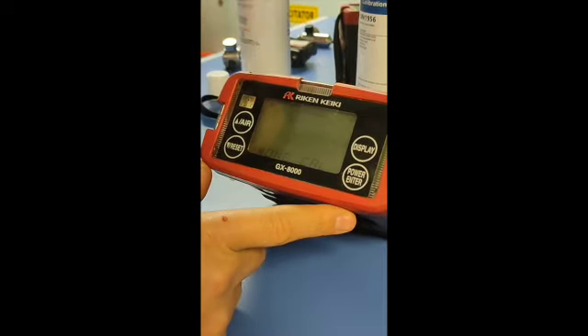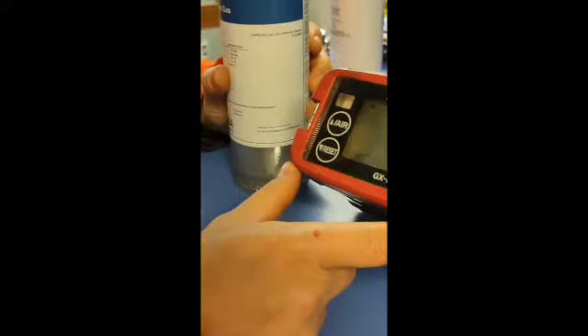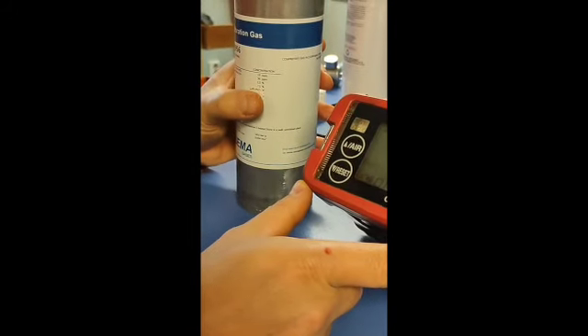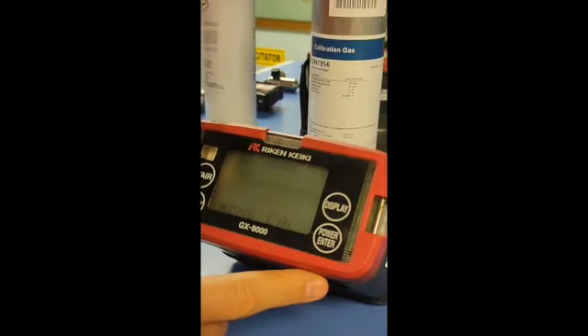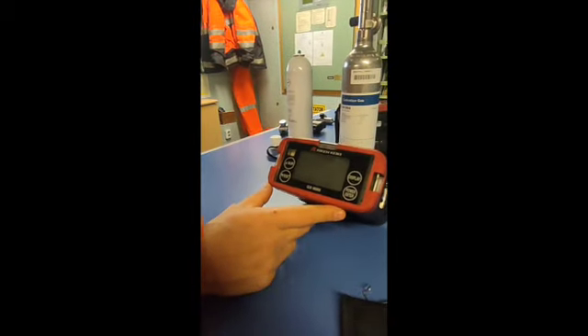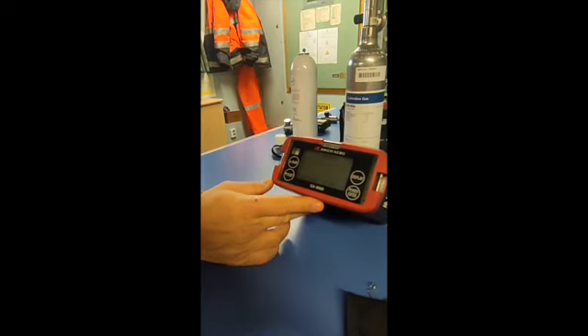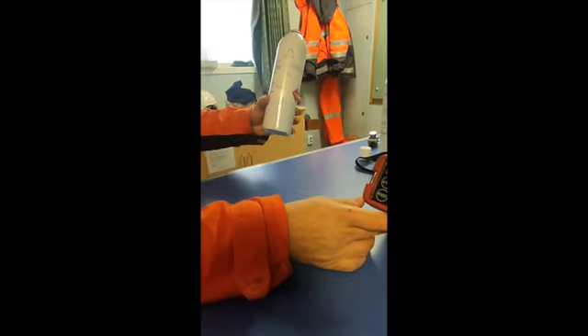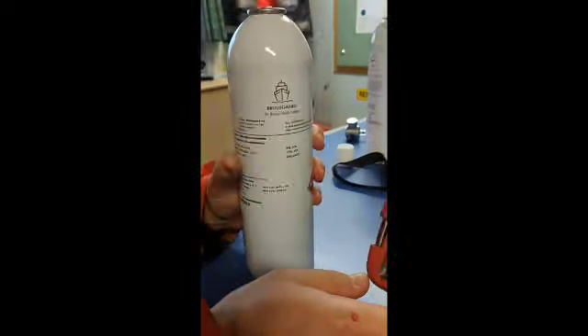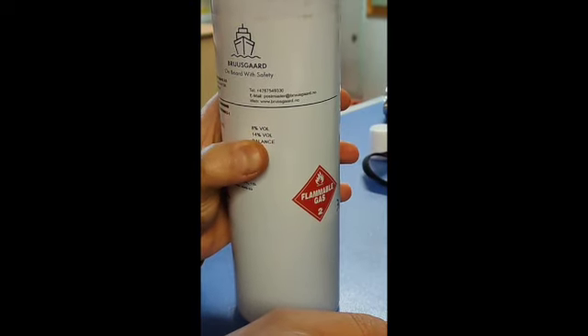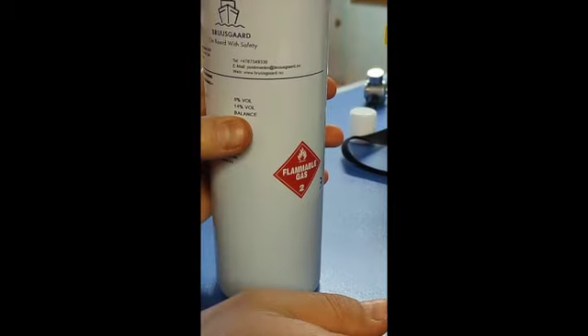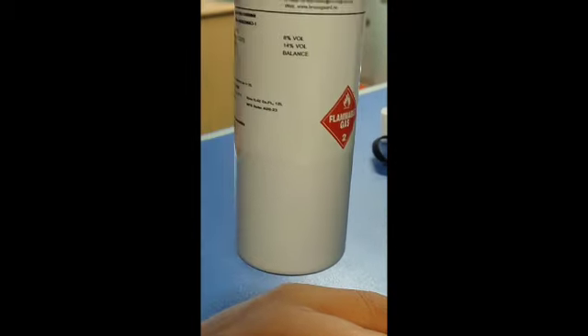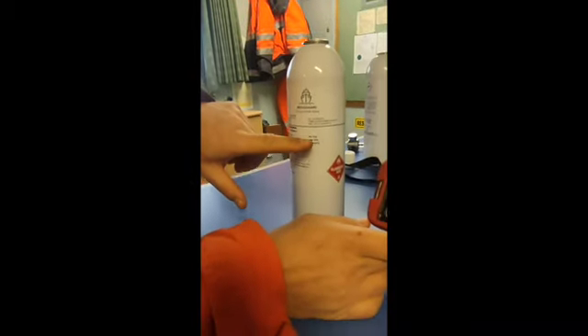But as we said before, the hydrocarbon percentage per volume sensor works in an inert atmosphere. But here I have 12% oxygen. So I cannot span gas my hydrocarbon percentage per volume sensor with this button. So I have to use another button. I'm using N-butane 8% volume in nitrogen balance. This gas is in an inert atmosphere. So I know the value, 8% per volume. I will see 8% also here.